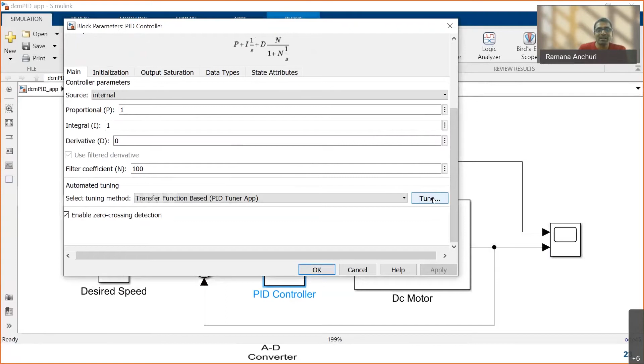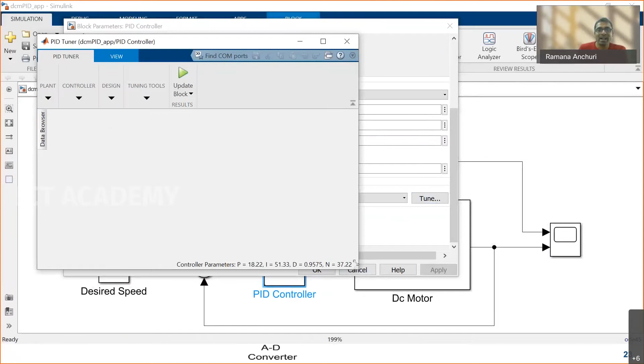So once you do that, what Simulink does in the background is it takes this plant model and there's an algorithm that runs in the background which gives you a tuned response. Now, if you observe, the dotted line response is the block response, which has the gains 1, 1, 0. And the tuned response is something like this, which is pretty much what we actually see for a unit step response. This is the response of the plant, right? Now, what are the gains that the system has already come up with? You can just click on show parameters and you see the tuned gains are this. And the block has these values currently. So with these values, the performance is not proper. That's where you can automatically tune it.